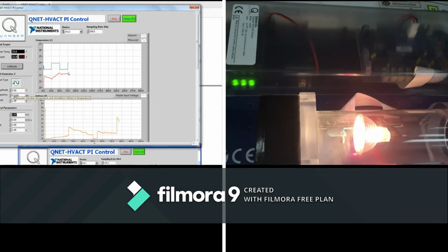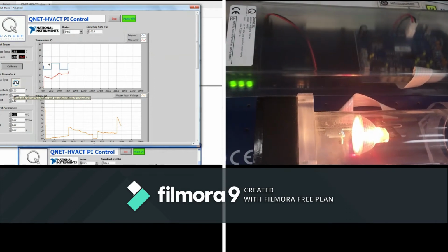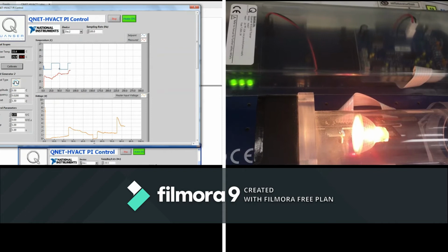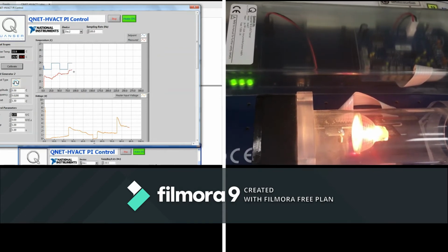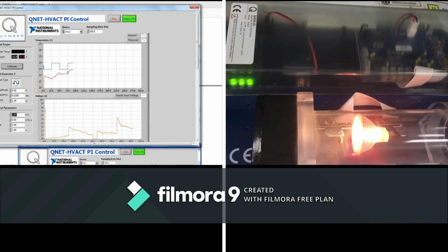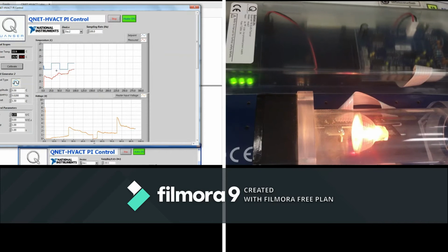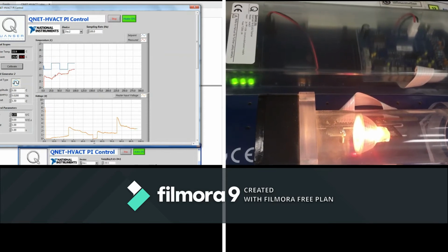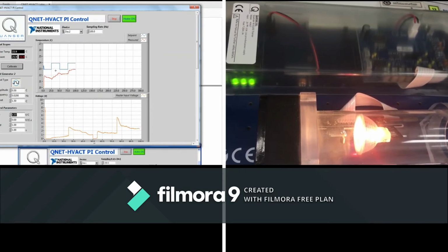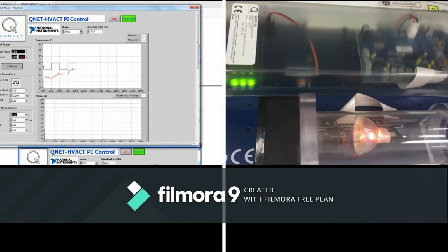The good thing is that we can compare with cycles. So this full cycle going up, straight and down, we will wait for the second cycle to be completed and then compare the result. So now you see this is far from the set point, this is close. The actual temperature was very far, and now it's much better.